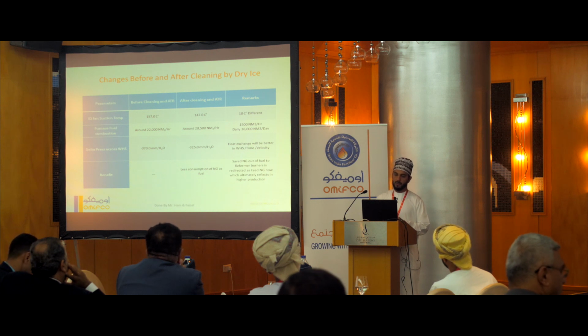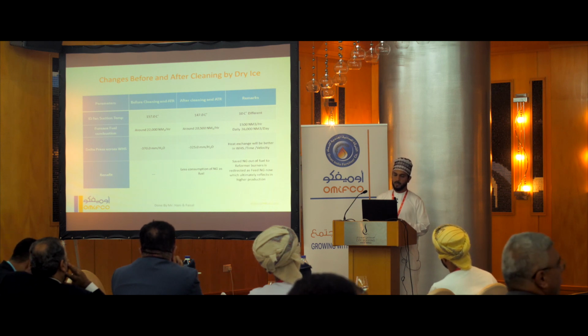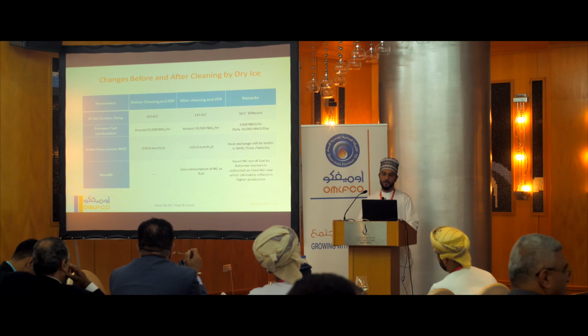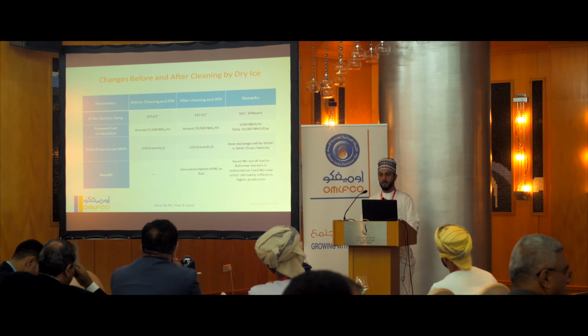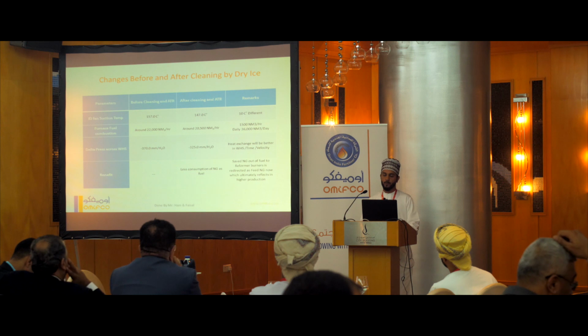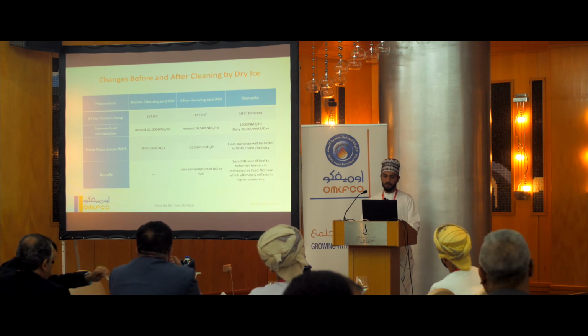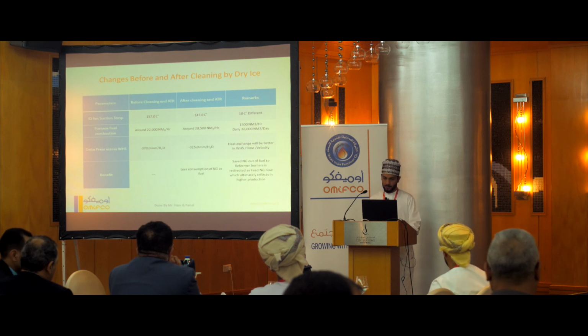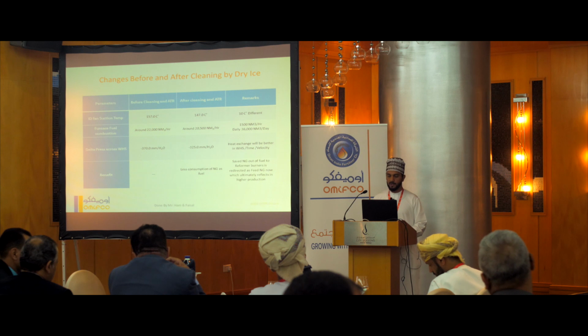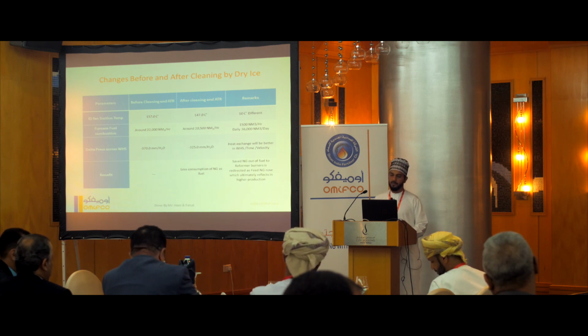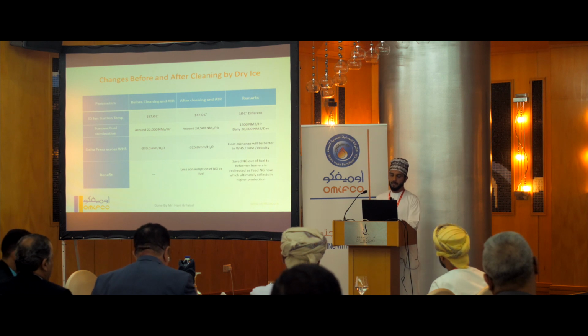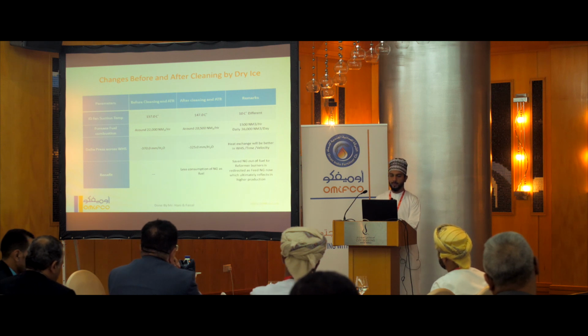And also, the delta pressure was minus 370, and now it is minus 325. That means the heat transfer will be better, and the velocity will be less. So heat exchange will be more. We are utilizing the waste heat of the flue gas temperature to heat the other coils. And the main benefit is that we get less consumption of energy as fuel. So we save energy at the fuel reformer burners, returning to the fuel feed, which ultimately reflects in higher production. So we are getting roughly 10 to 12 metric tons per day of ammonia by using this.